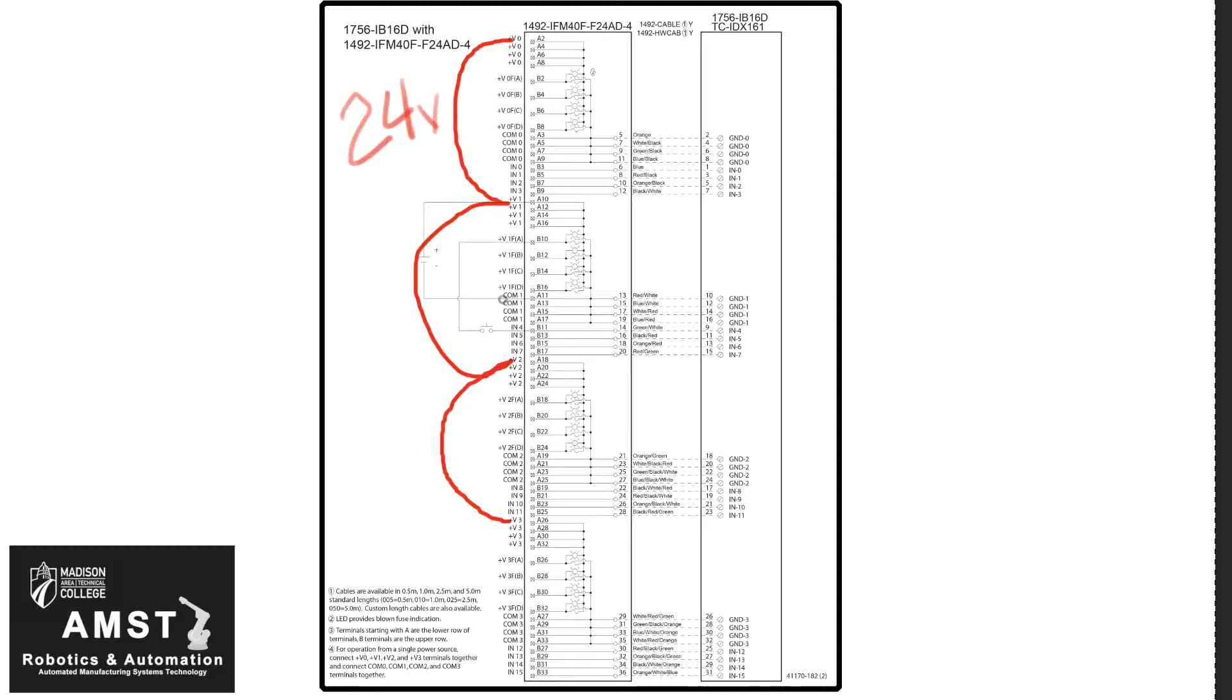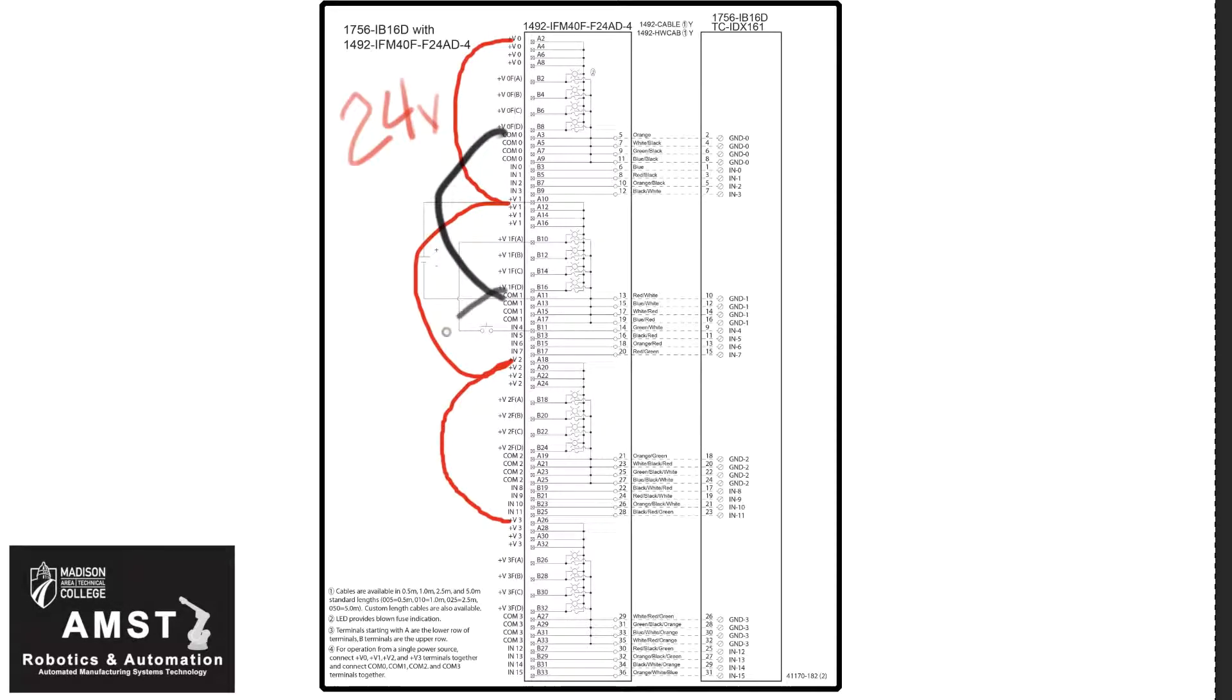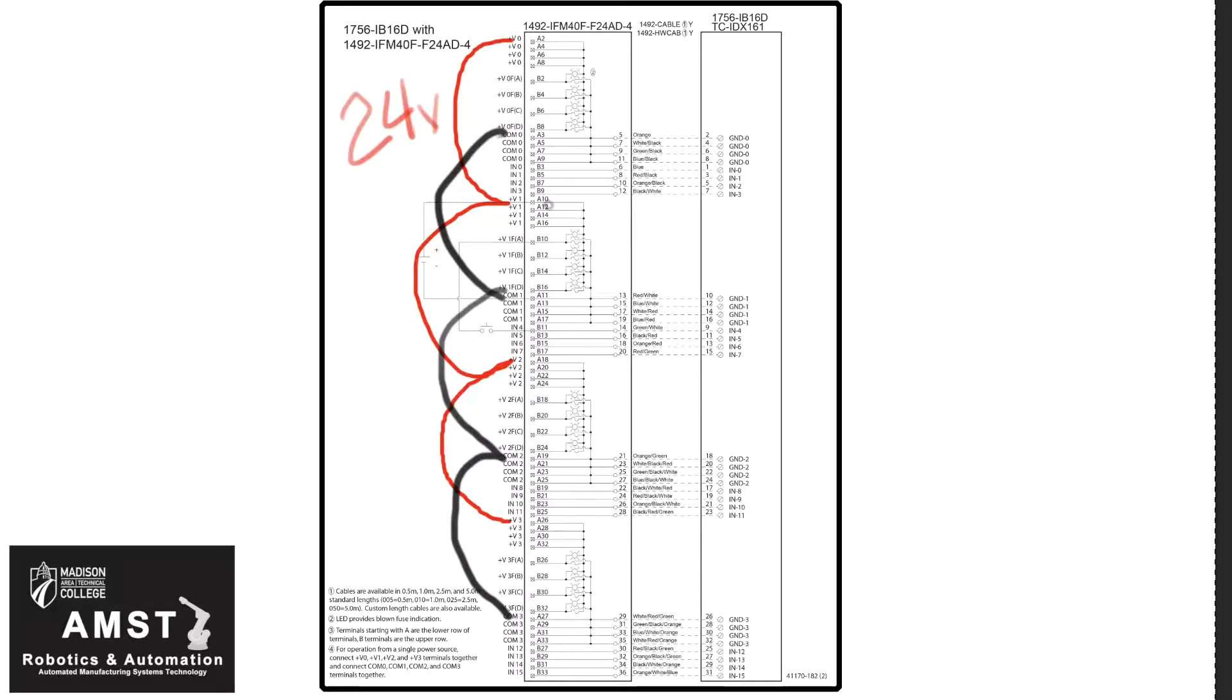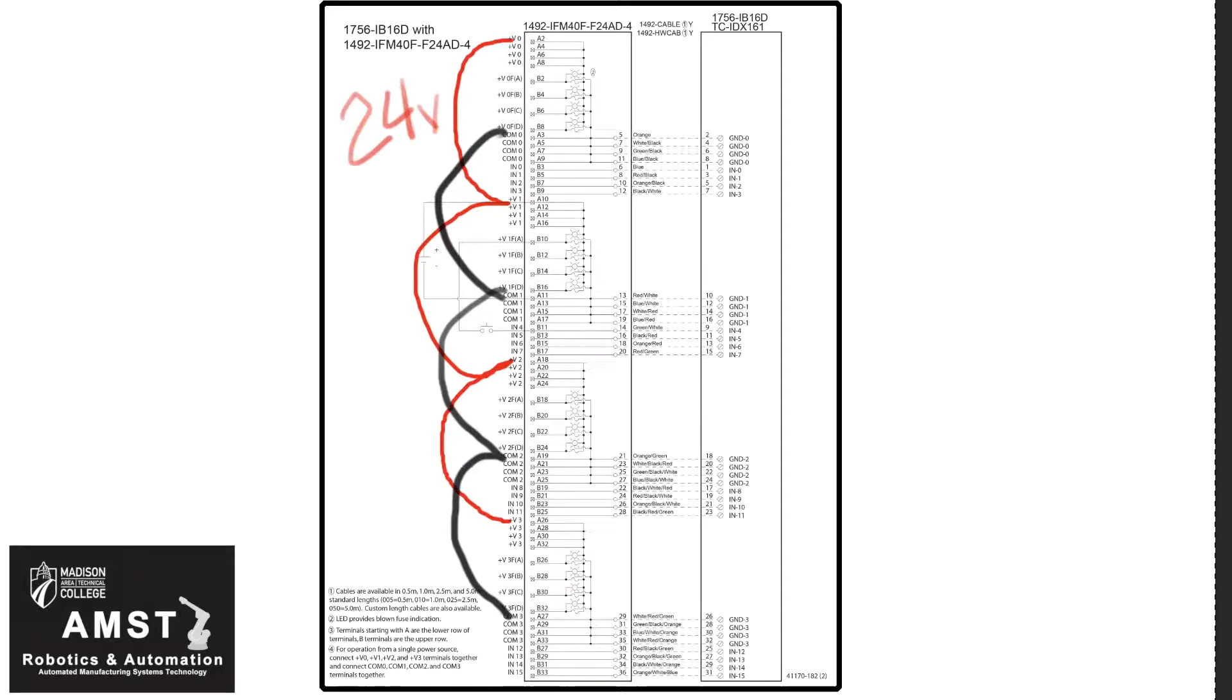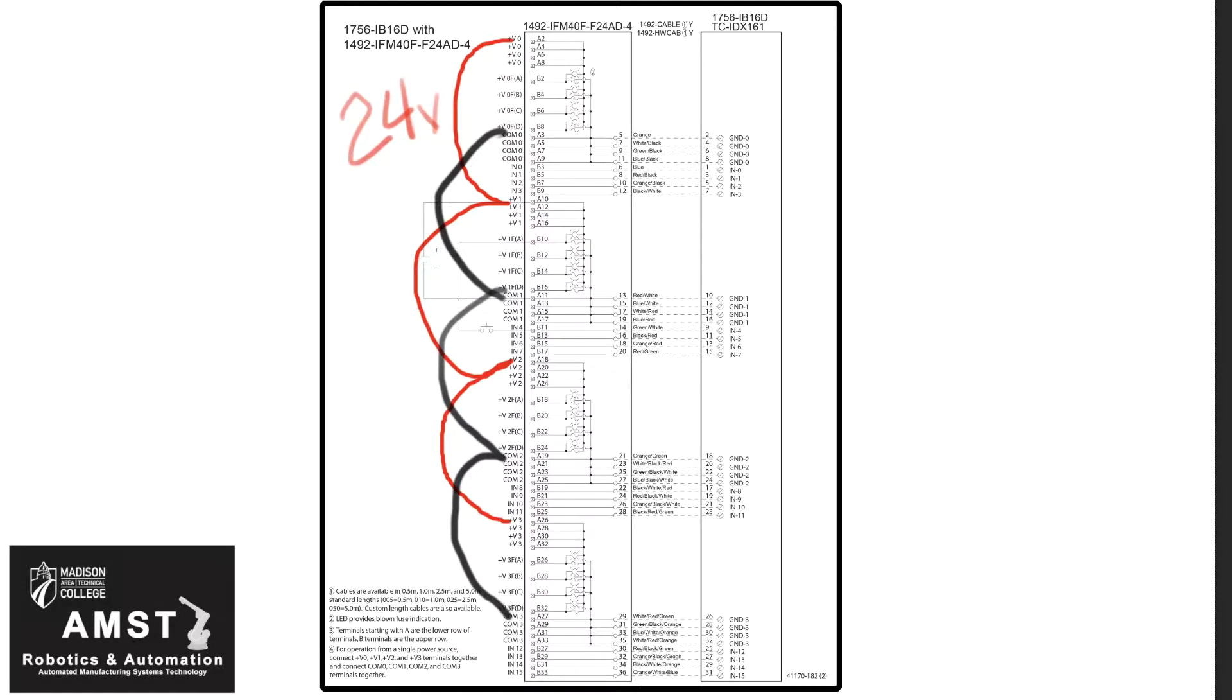Next, we can connect our commons, common zero to common one, to common two, and common three. Now this is assuming that all your field devices are going to be 24 volt, and that your power supply can handle enough amps to supply all the field devices, all 16 field devices, with one power supply.